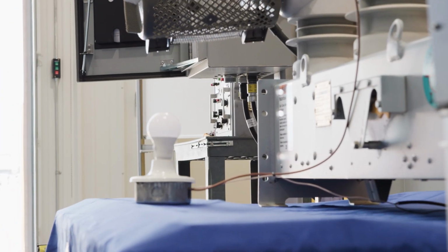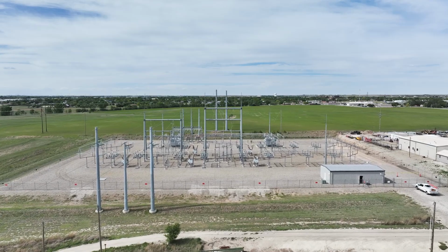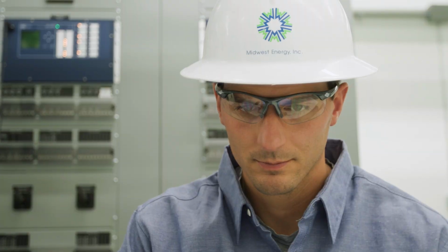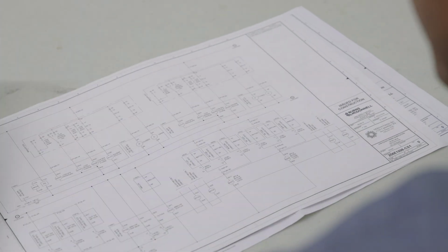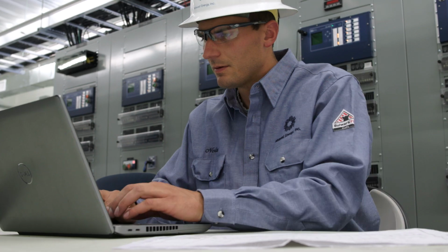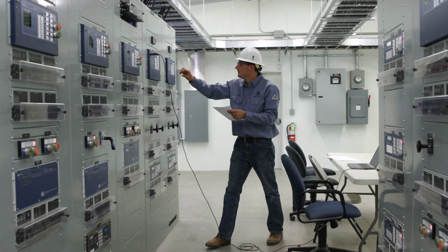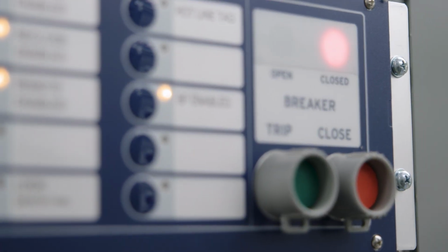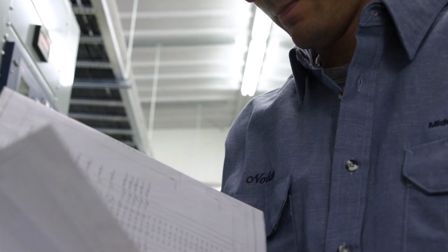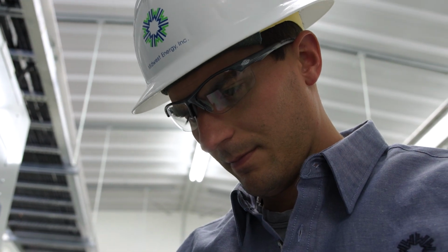The second part of the installation process occurs out in the field. Relay technicians install the programmed relays at new substations, conduct maintenance on relays, or even replace older devices. I continuously test the relays around Hays to make sure they are operating correctly. When they aren't, I make repairs and reprogram them.